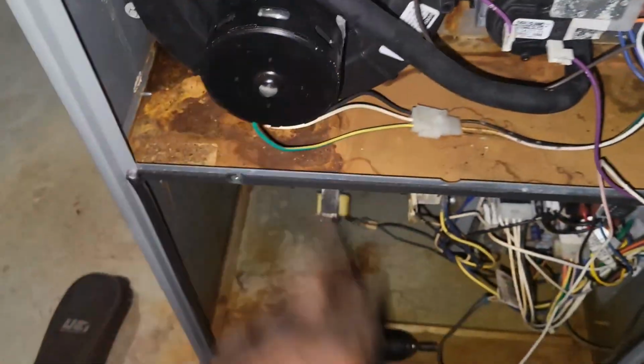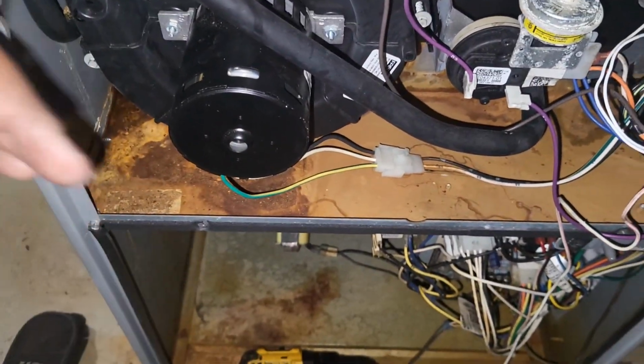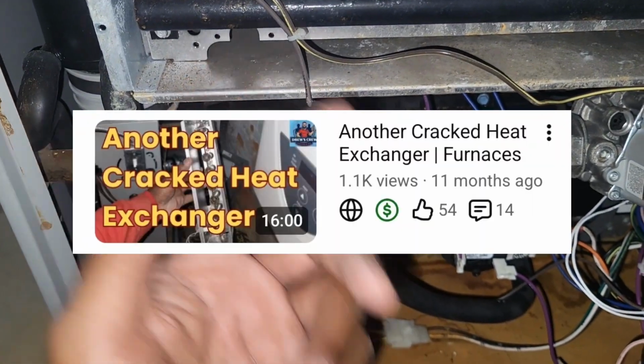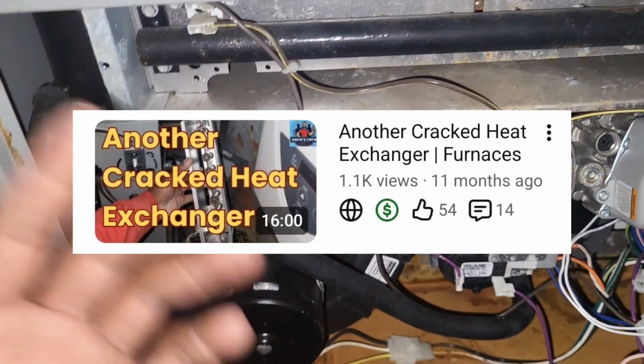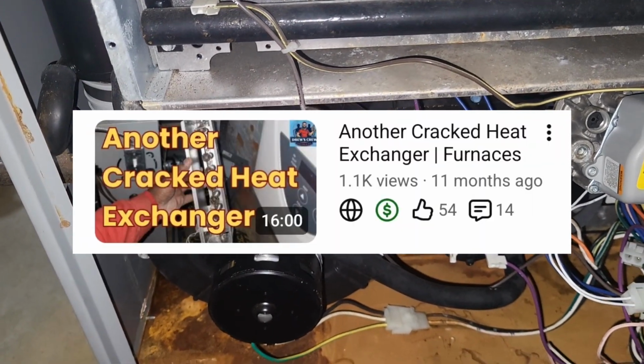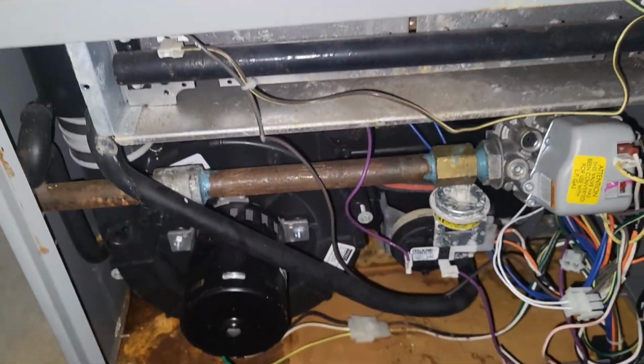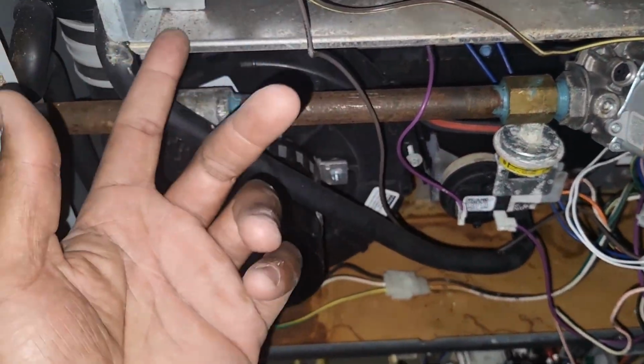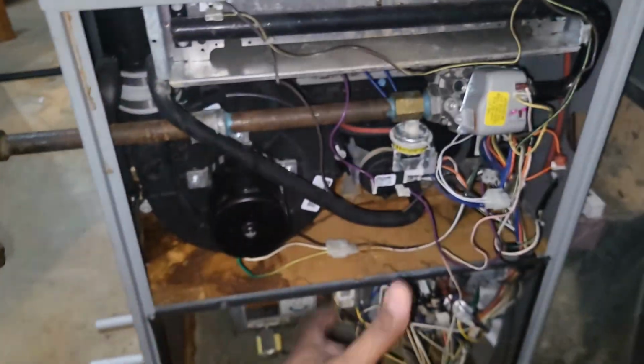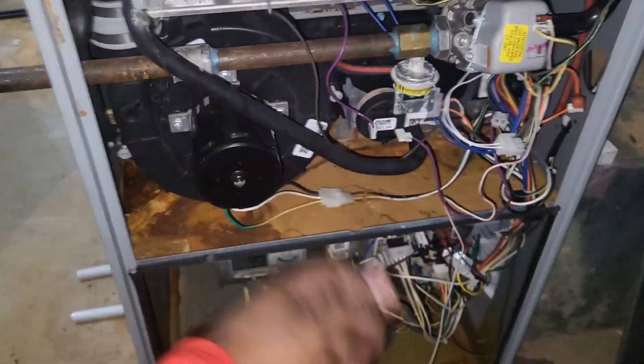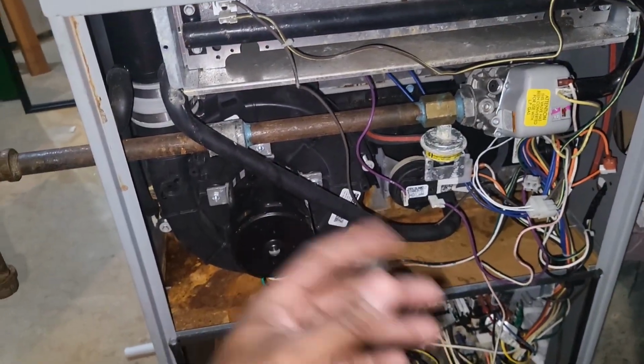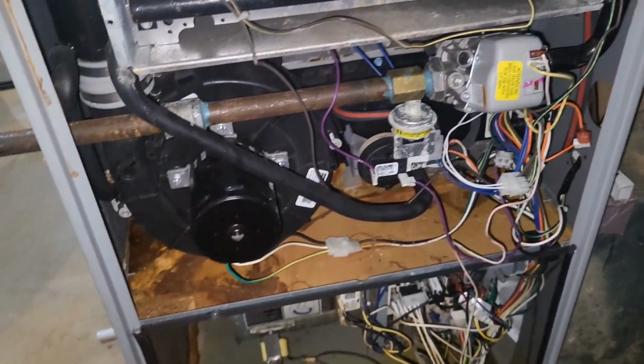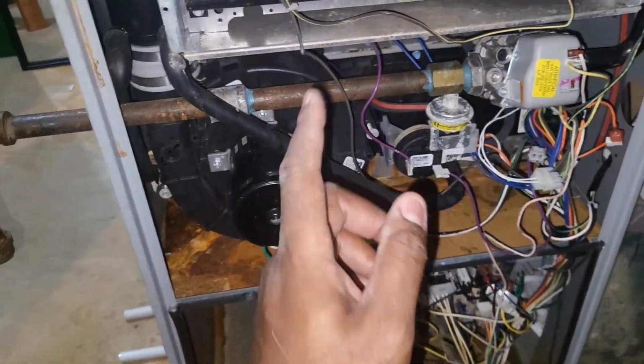But guys, I had an estimate about a year ago, and that furnace is oversized. That was the furnace that was shooting flames out the burners, and we had to red tag that furnace, and we recommended replacing it. Now, the issue wasn't with the heat exchanger. The issue was with the furnace being oversized, which cracked the heat exchanger. The heat exchanger definitely had a hole in it, but that wasn't normal wear and tear. I think that one was a Ducane furnace as well.